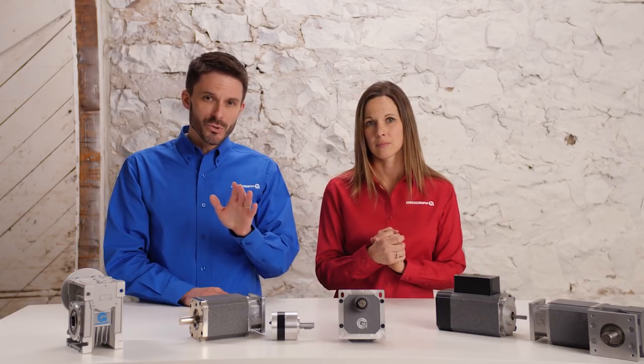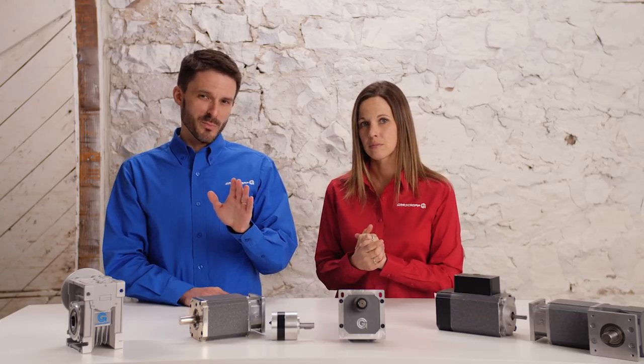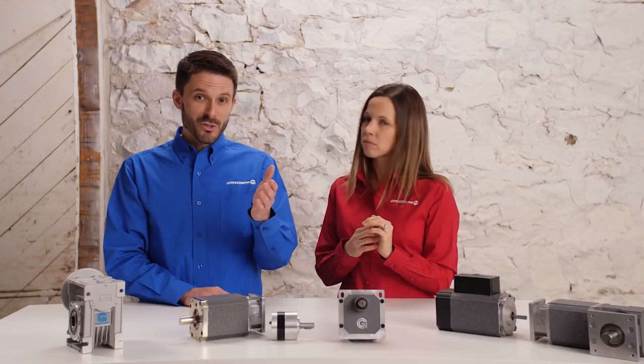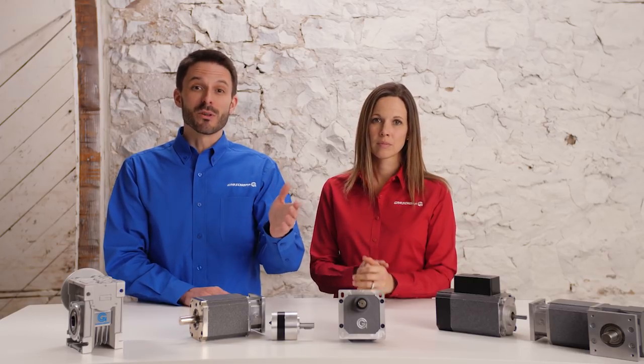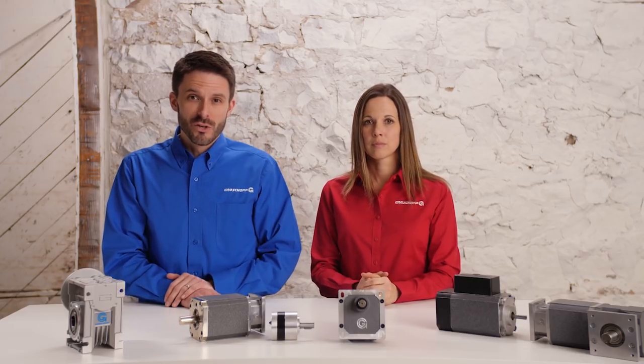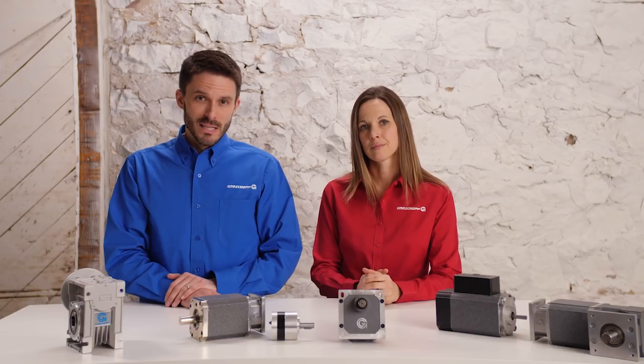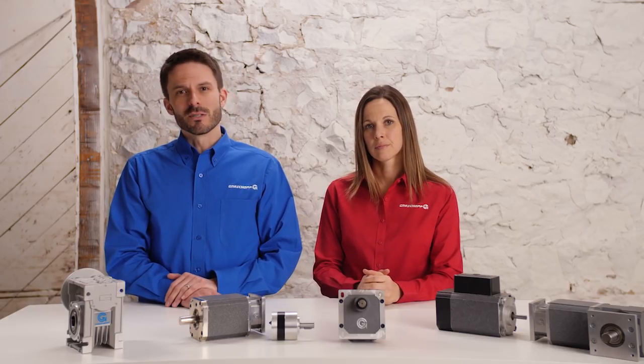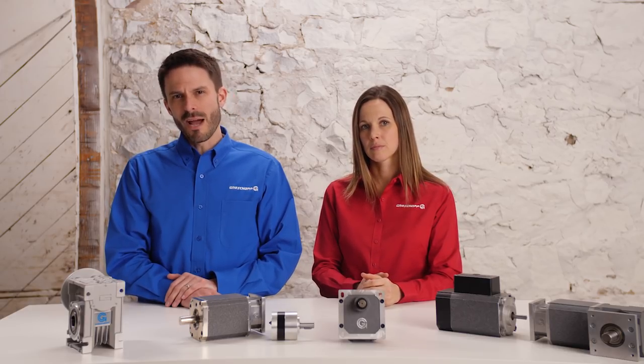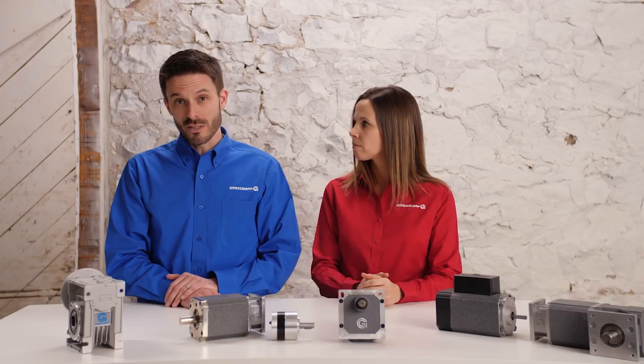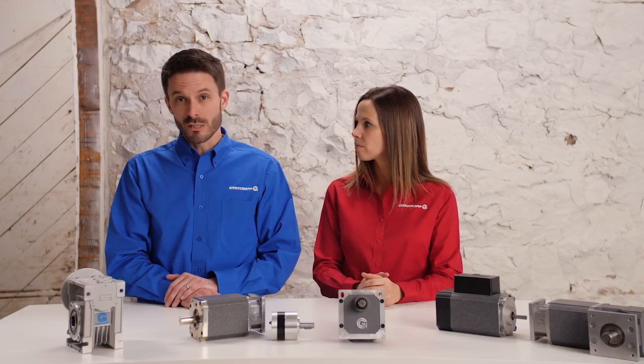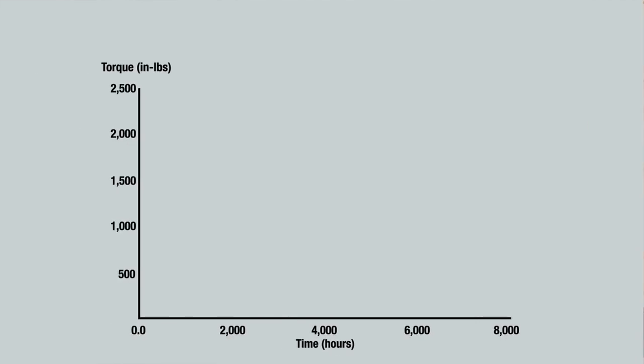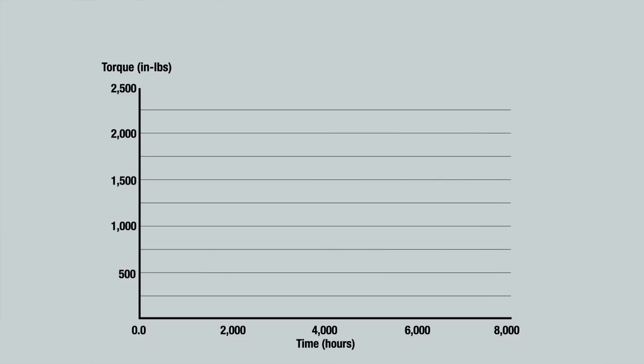Notice we aren't talking about reducer ratios at this point. Even though it will impact the torque rating, it's typically determined later in the process during the motor selection. The first step to determining output torque is to match the life requirements of the gearbox using the gearbox manufacturer's life curve.